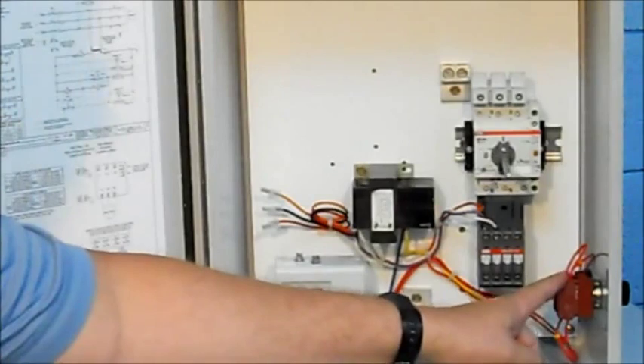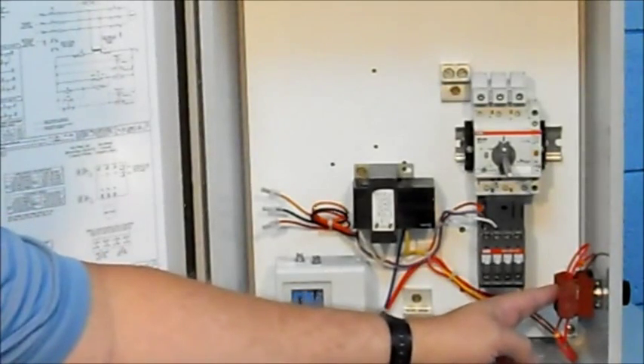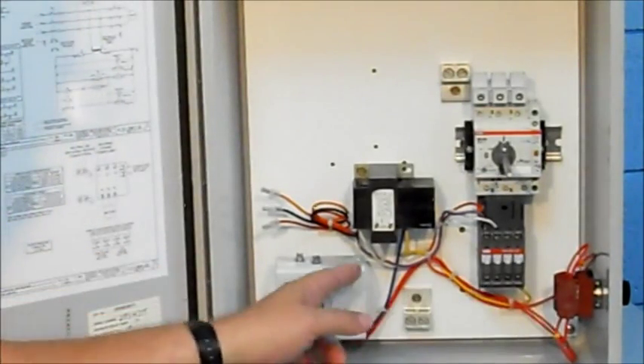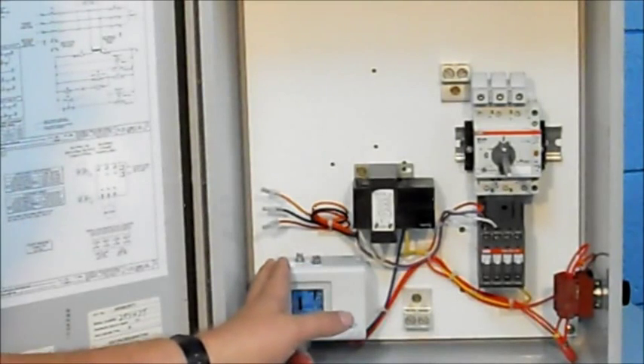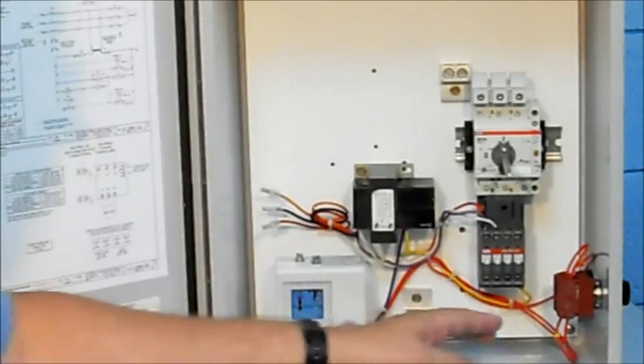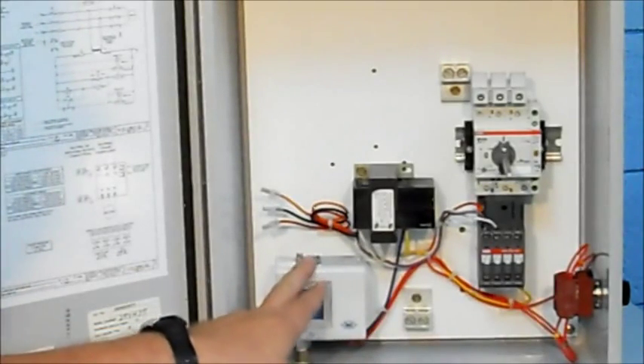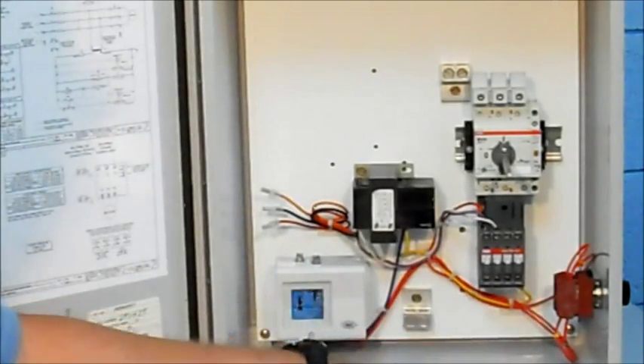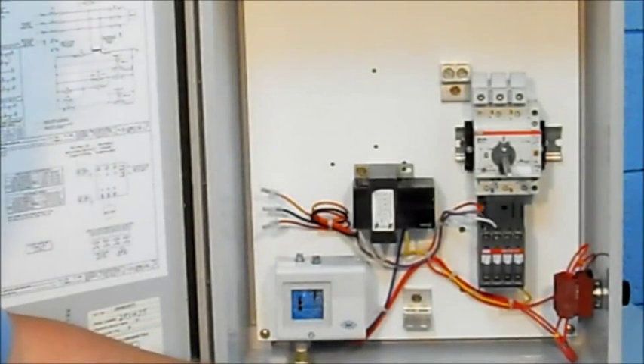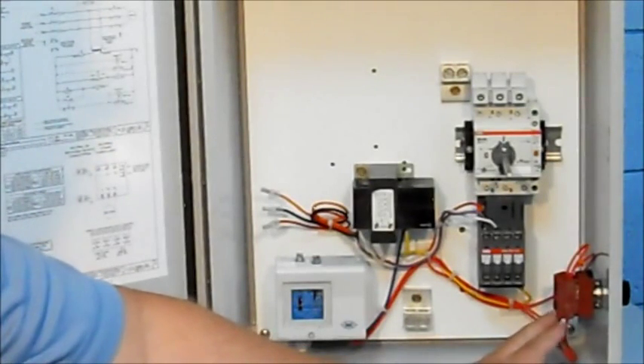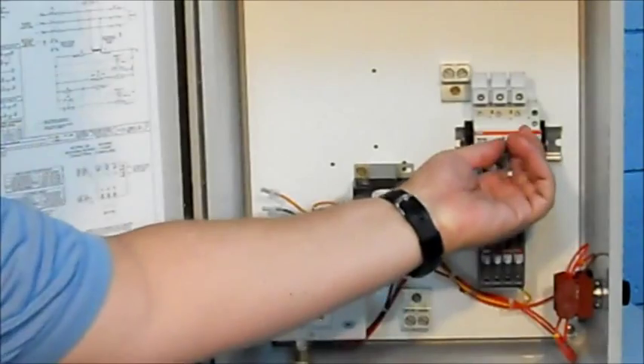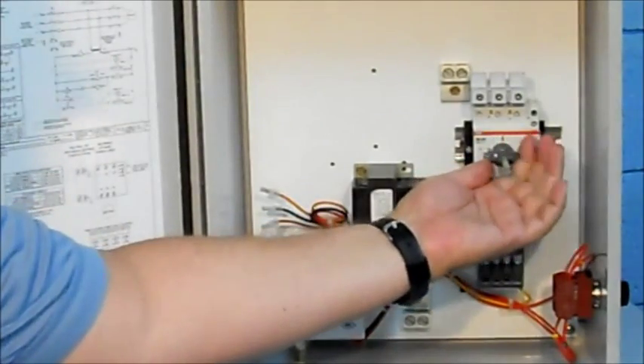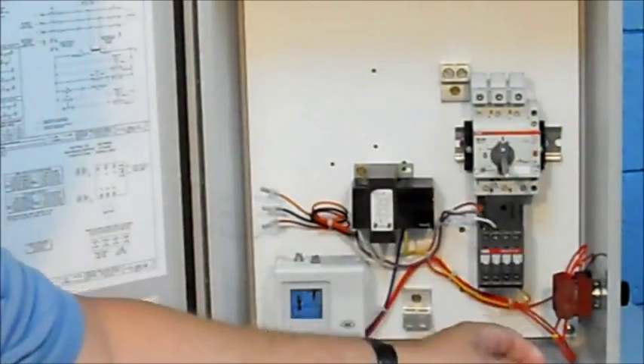First goes to the selector switch, the hand off auto selector switch, and over to the pressure controller, the pressure switch in this unit. Whichever of these two devices calls for the pump to run will determine when the pump starts and stops. The hand off auto selector switch has an off position which turns the jockey pump off, as well as turning off the disconnect will turn off the jockey pump.